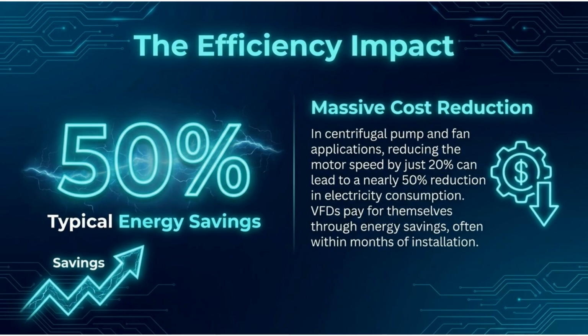The efficiency impact is significant. In many applications, a 20% motor speed reduction can lead to nearly 50% energy savings. These massive cost reductions mean VFDs often pay for themselves quickly.